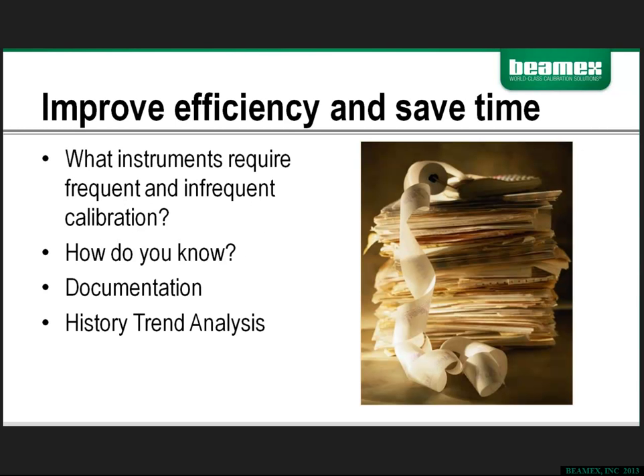When an engineer buys a particular sensor, the instrument manufacturer provides technical specifications, and those include details regarding the maximum drift of that sensor over a given period of time. Through proper documentation, meaning the use of Beamex documenting calibrators and CMX calibration management software that has the CMX history trend option installed, that engineer can now verify that the sensor he or she has purchased actually performed within the specified tolerance over a certain time period. If it hasn't, then that engineer now has data that they can present to the manufacturer or vendor that will support their findings, and history trend will allow you to analyze drift over certain periods of time.